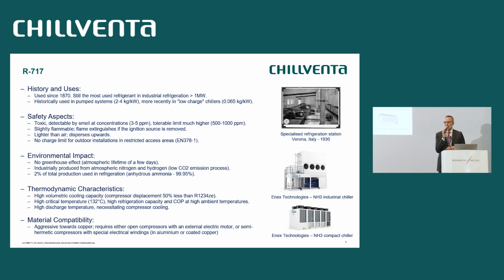But more recently, we have developed low charge chillers. You may have heard this word several times, but what does that mean? Basically, there is not an official definition of low charge. For example, some people say below 1.3 kilos per kilowatt is low charge, but actually our systems go as low as 65 grams per kilowatt. And clearly, when you have such a small charge, the safety is maximum.